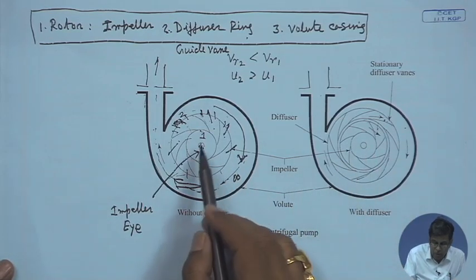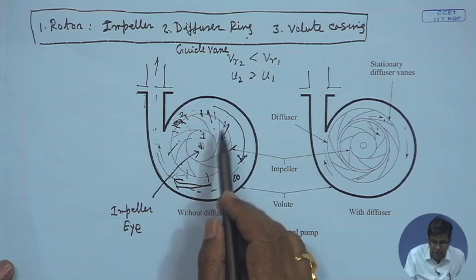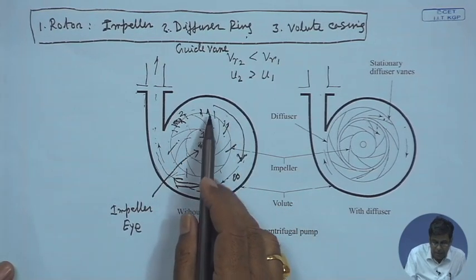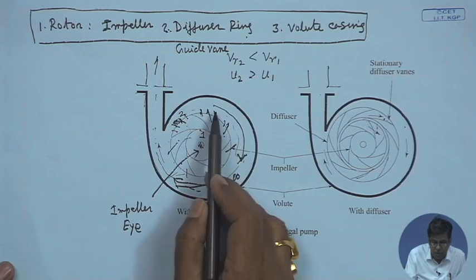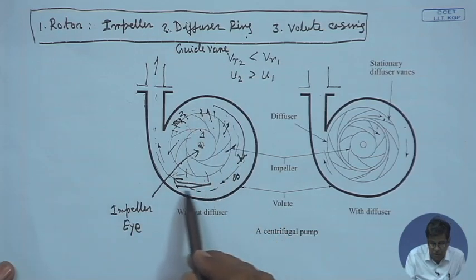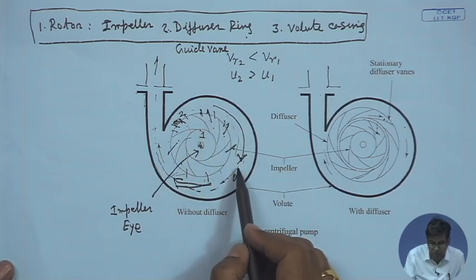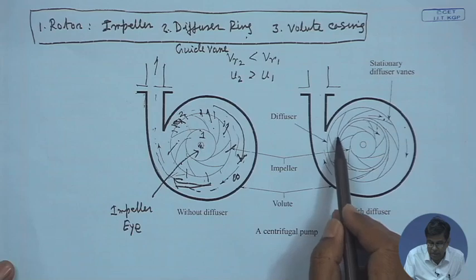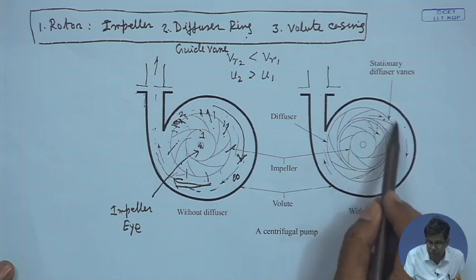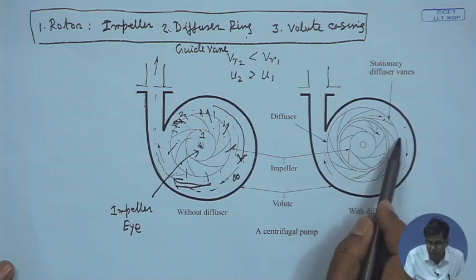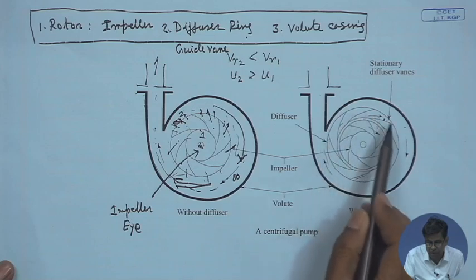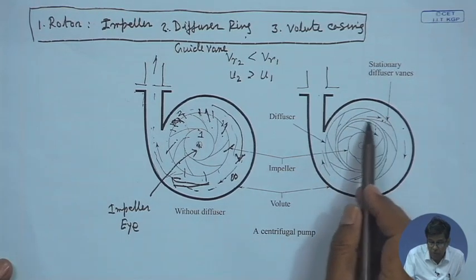To have better and more efficient diffusion — and diffusion here in fluid machines terminology means the decrease in velocity and increase in pressure in a flow — this passage is known as a diffuser passage or diffuser. To make this process more efficient, we sometimes use a vane diffuser, where there is a ring to which the diffuser vanes are attached. Before going to the volute or scroll casing, the fluid flows through the vane diffuser. These diverging passages are fixed vanes, known as a vane diffuser.